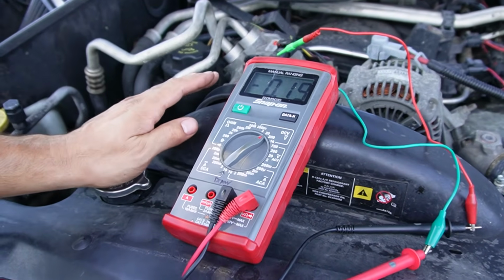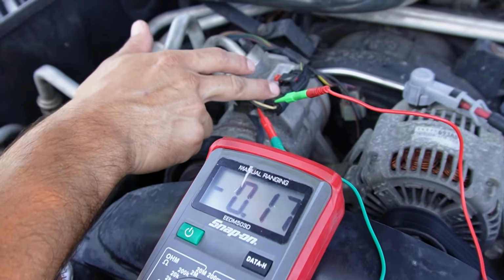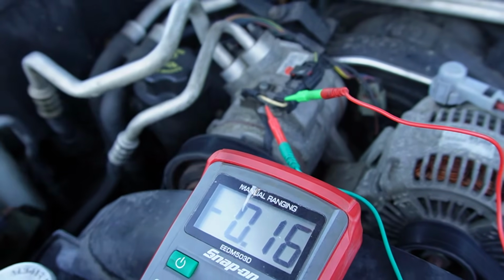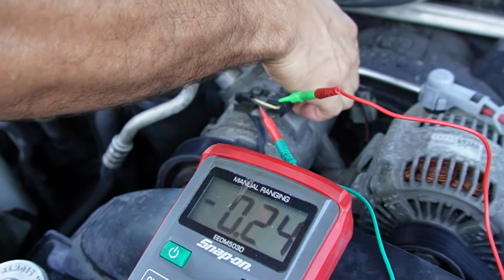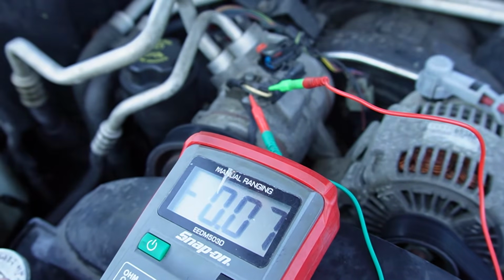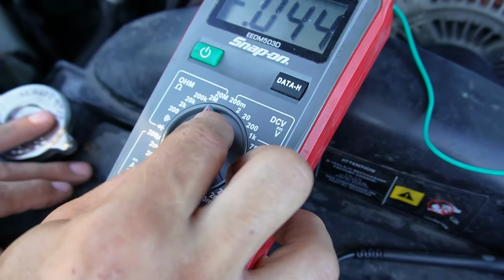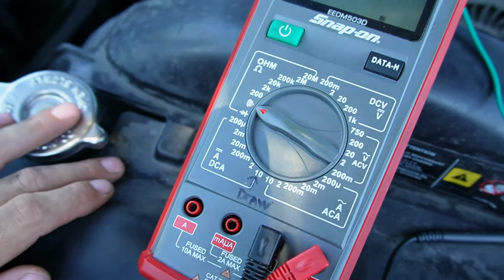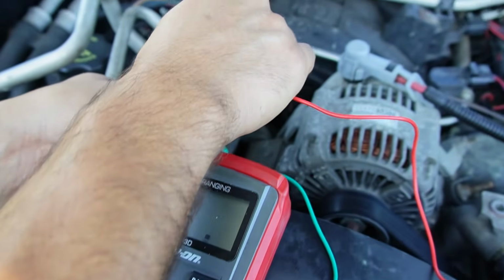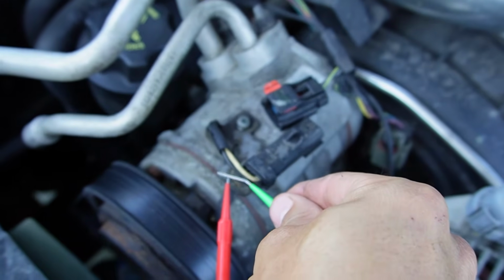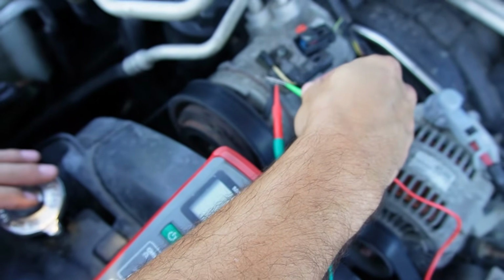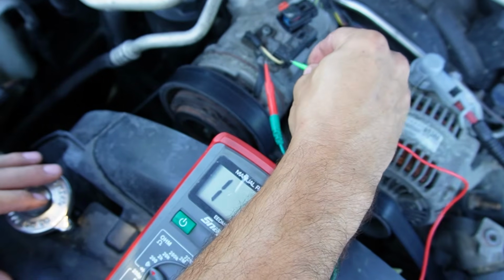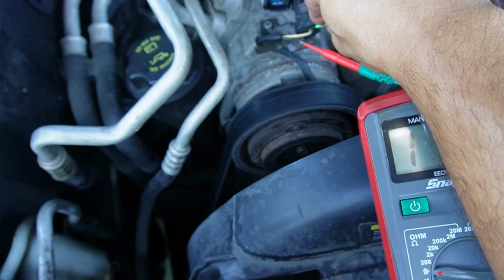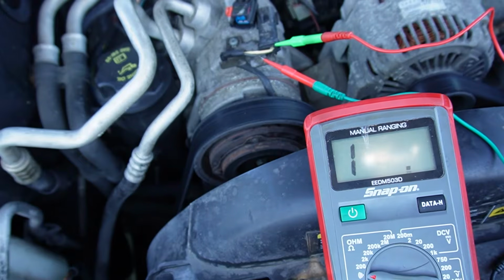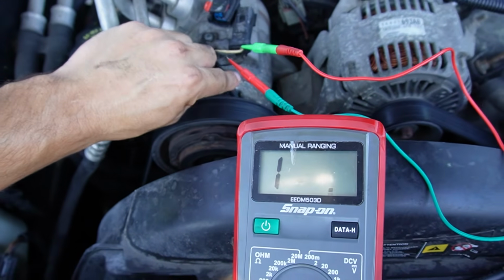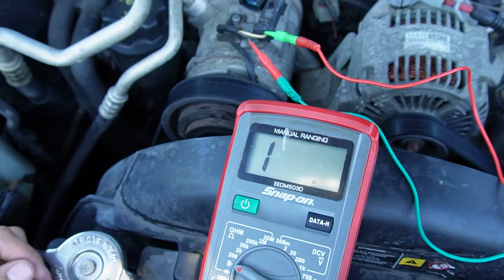So now that we have determined that there is voltage coming into the coil right here, what I'm going to do is unplug it and turn the meter into ohms, set it so that if the 2 wires touch there is an audible sound. You can see right here, there is no sound, so that tells me that the coil for this clutch is broken, it's done.